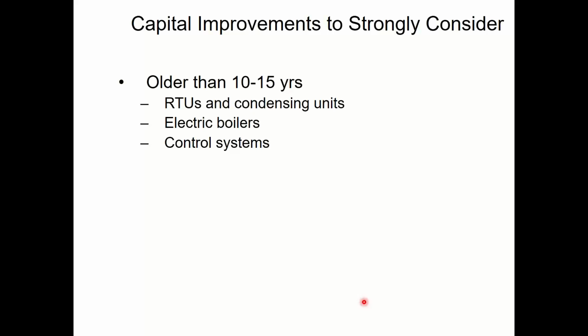So based on the last chart I showed you and some personal experience, this is what I would say. Your rooftop units and outdoor condensing units, if they're in that 10 to 15 year range, I would not be doing anything to improve them. Now, I'd still clean coils and stuff like that, but I'm not going to install extra controls on there. I'm not going to retrofit a VFD on a 15-year-old rooftop. I'm not going to put an economizer and demand control ventilation on a 15-year-old rooftop.